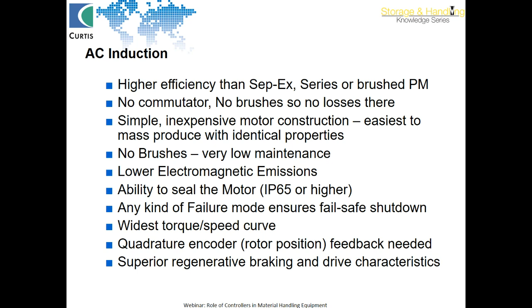It has the widest torque versus speed characteristic curve compared to the corresponding DC motors like series, separately excited and PMDC motors. It does require quadrature encoder feedback, that is the position feedback of the rotor from the motor shaft. It has regenerative braking from the max speed down to zero speed.